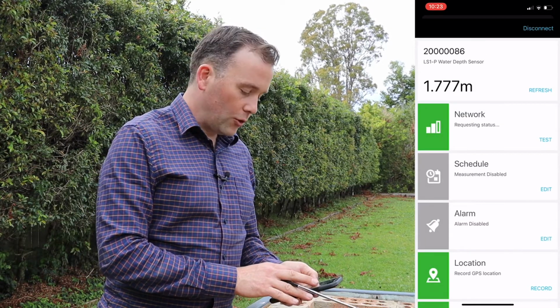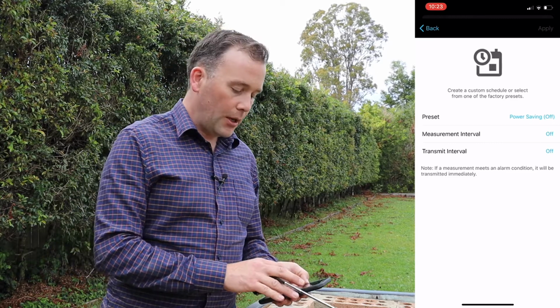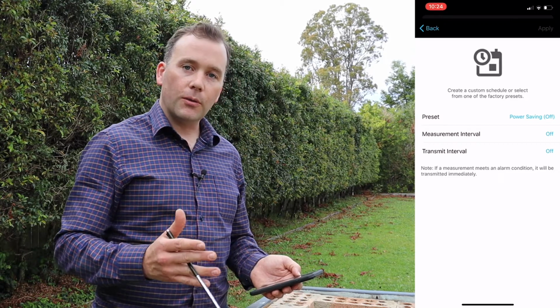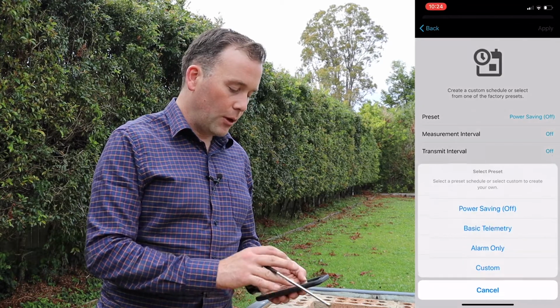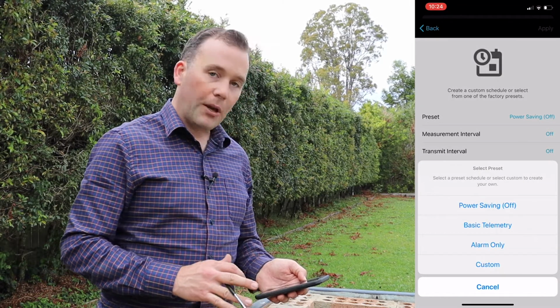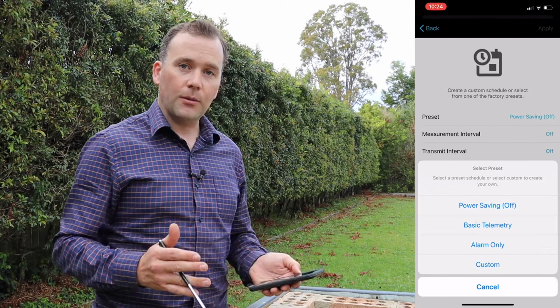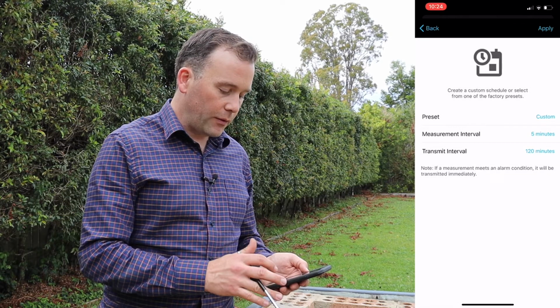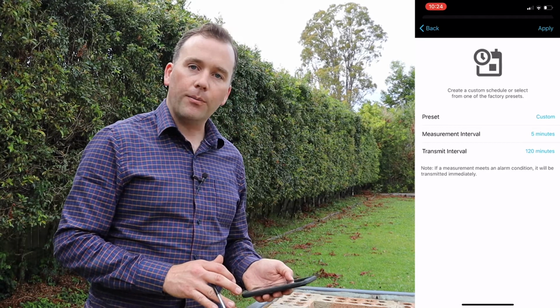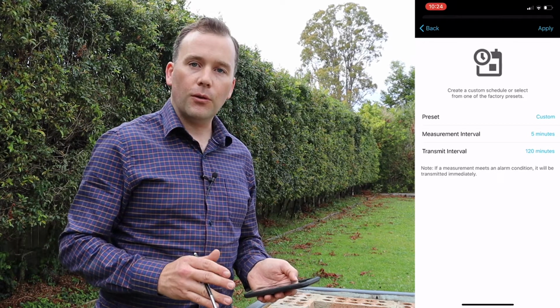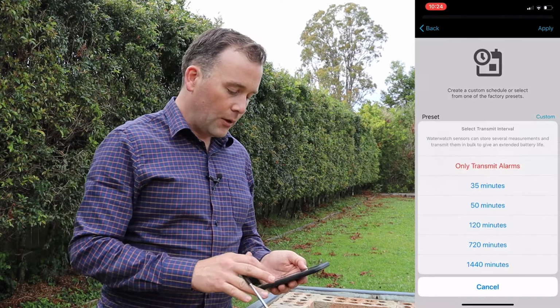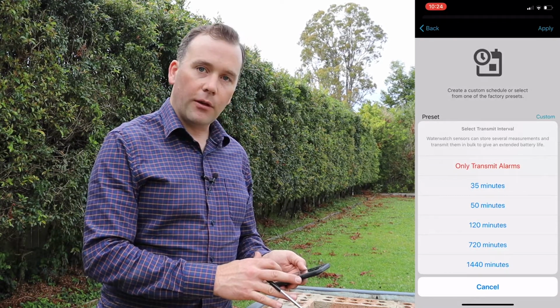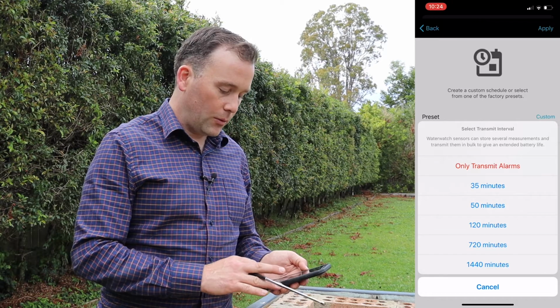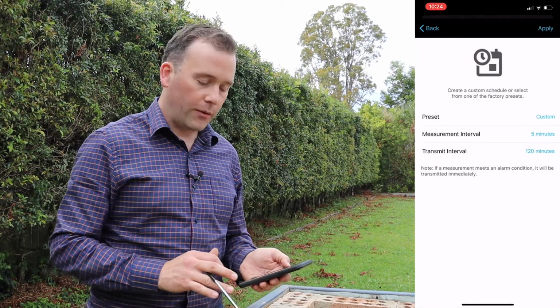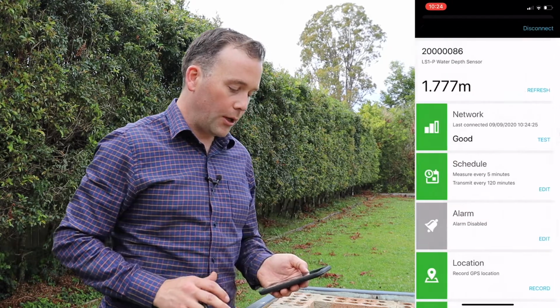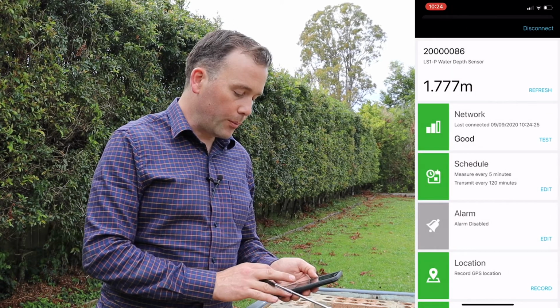Then the next section, we can schedule how often this device will talk. Out of the box, it comes in power saving mode, so it's off and it's not wasting your battery. We'll go into there and we can change to either basic telemetry, alarm only, or customized. So basic telemetry, there's a default here of reading the bore every 5 minutes and transmitting to the server every 2 hours with all those 5-minute readings. You can of course change that, as you can see here, to a 35-minute report, 50, and so on, to whichever transmit time you like. We're just going to leave it on 5 minutes and 2 hours for now, so we'll hit apply on that. So that's scheduled to report.